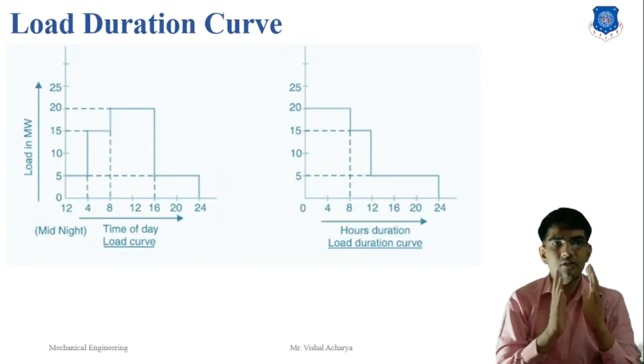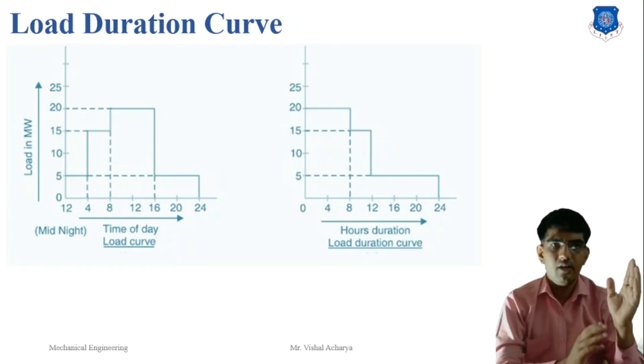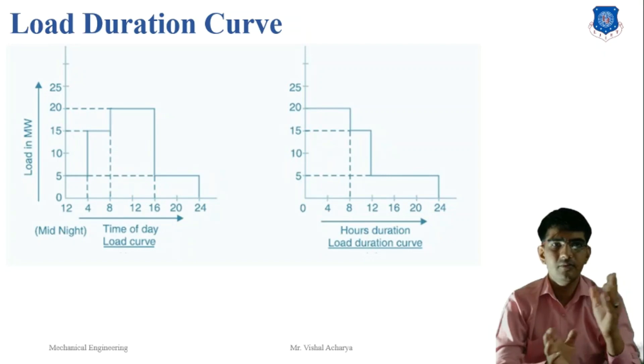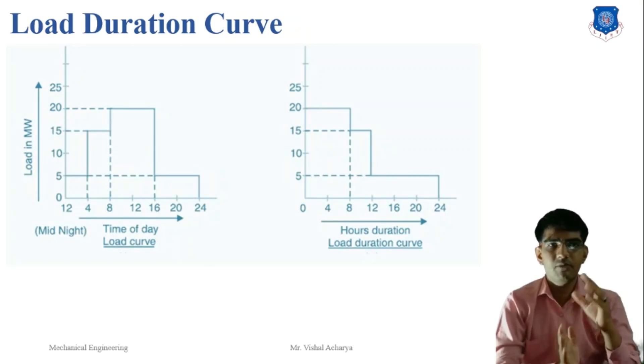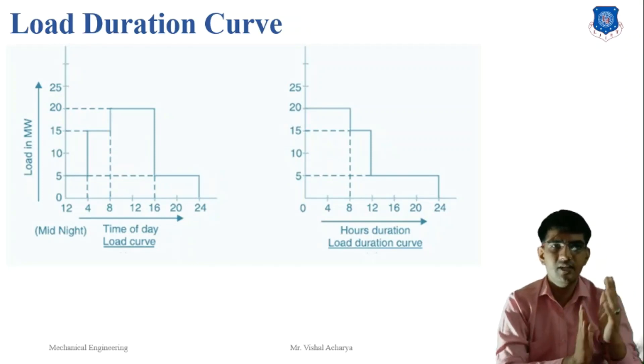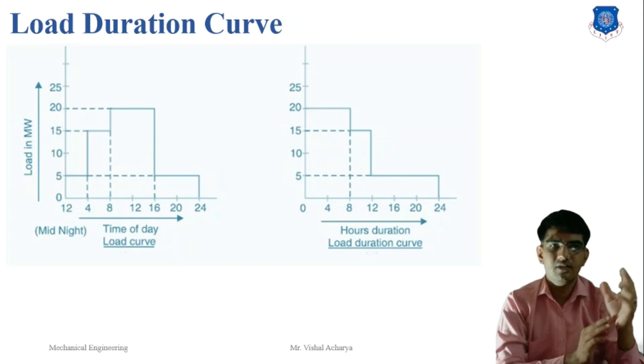The load duration curve is defined as the curve between load and time, in which the ordinate represents the load plotted in order of decreasing magnitude — with the greatest load at the left, lesser load toward the right, and the lowest load at the extreme right. To plot the load duration curve: first, present the load curve; second, note the total time duration during which each load occurs; and last, plot the load against the time during which it occurs.